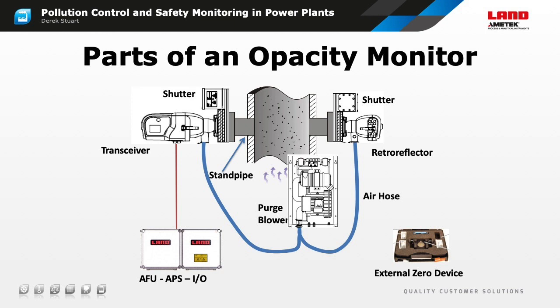Opacity monitor accessories include an air purge system to protect the sensitive optical components from the hot corrosive stack gases, fail-safe shutters which prevent damage to the optics if the air purge fails, and also allow the user to isolate the instrument from the stack. This is especially important on positive pressure stacks, where the operator can be exposed to flue gases when the instrument case is open for maintenance or calibration.